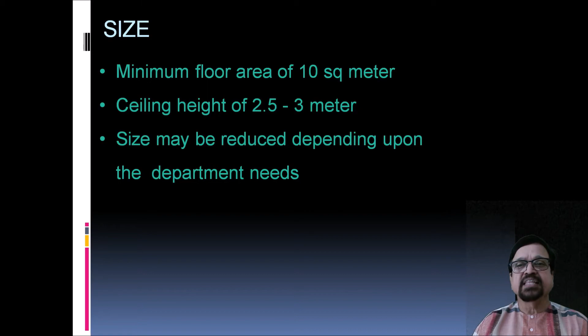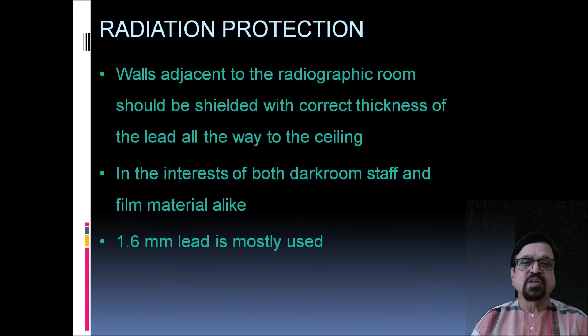Now we'll come to the radiation protection and protection required in a dark room. Walls adjacent to the radiographic room should be shielded with concrete or lead all the way up to the ceiling. In the interest of both darkroom staff and the film material kept in the darkroom, 1.6 mm lead is mostly used. So either 9-inch concrete or 1.6 mm of lead is recommended in a darkroom where the staff is working and where the films are.